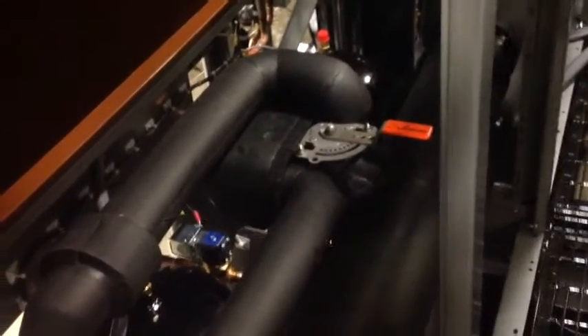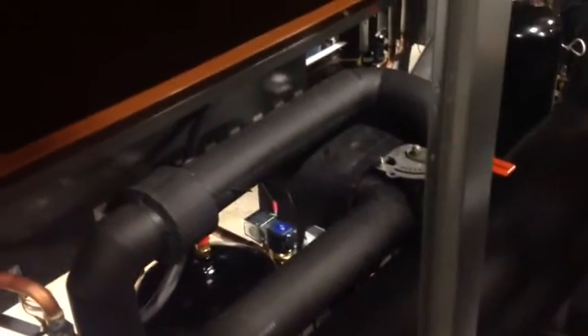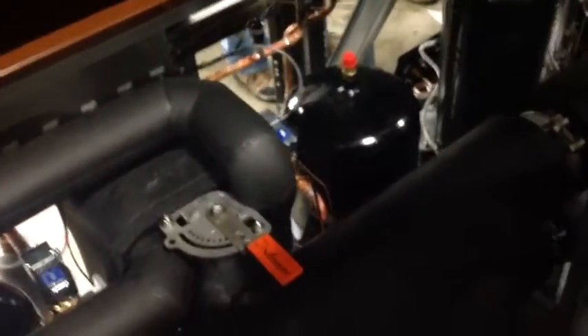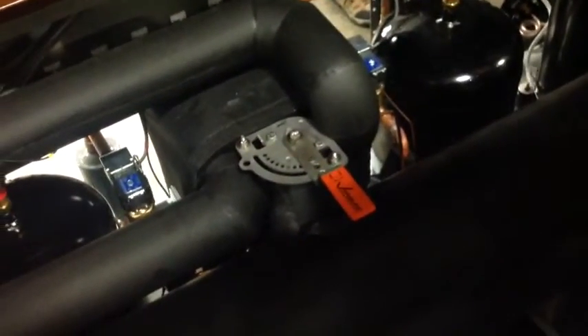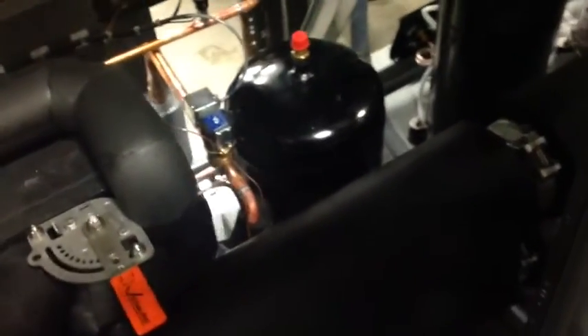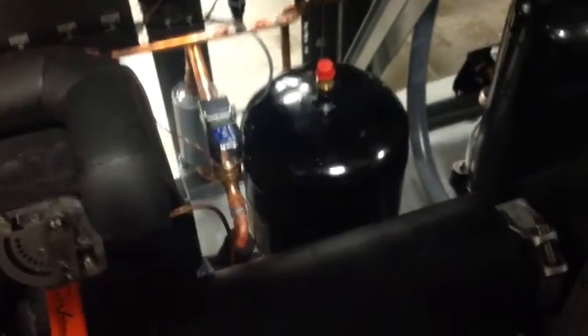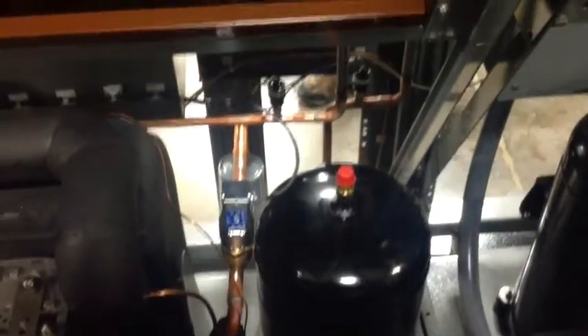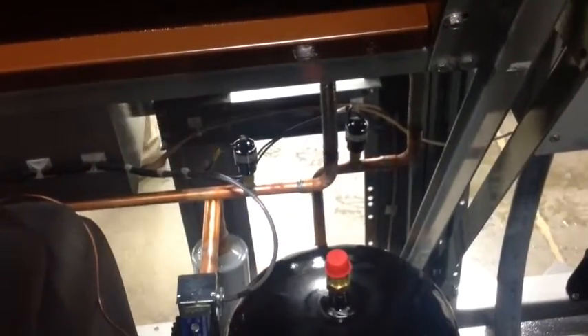Compressor 1, compressor 2, one of the liquid line solenoid valves, isolation valve, which is on both the top and bottom water connection to the braze plate evaporator, and now you can see the 2 receivers off to the right hand side, 1 and 2, and that's because this chiller utilizes independent refrigerant circuits. Those are the high pressure switches for circuit A and circuit B.